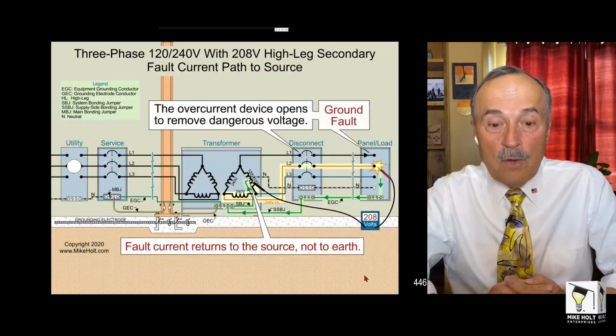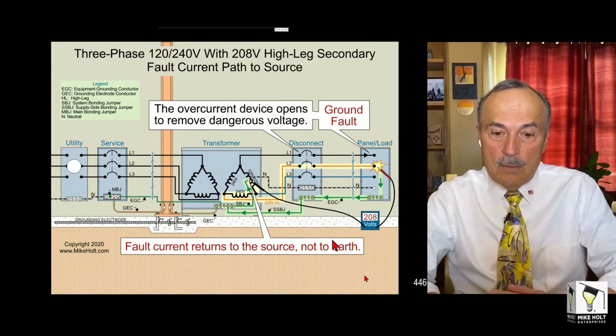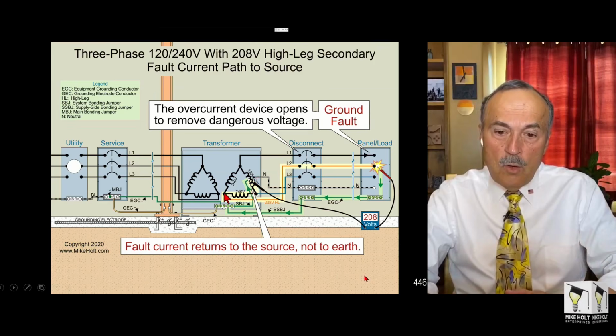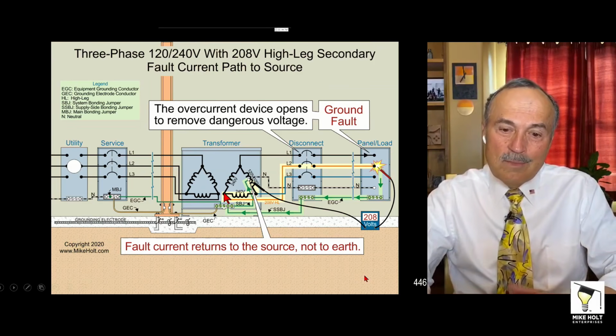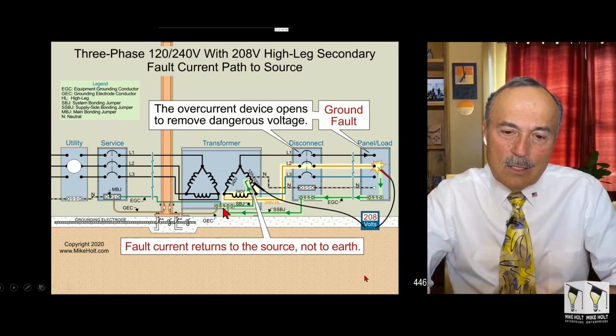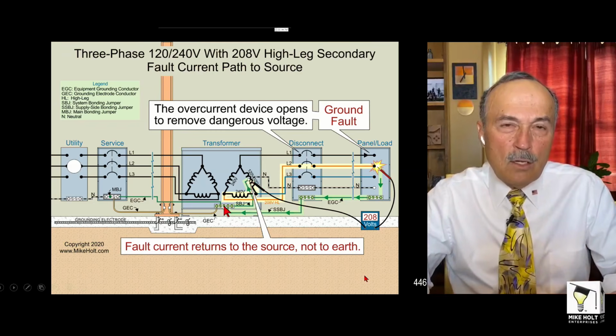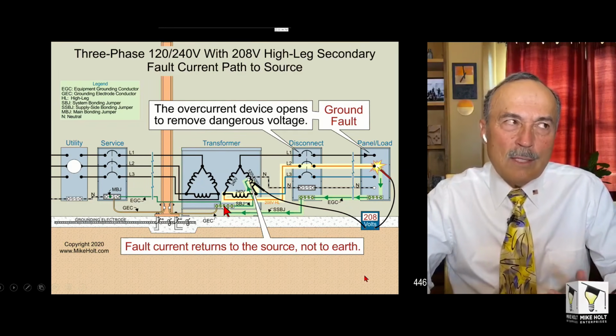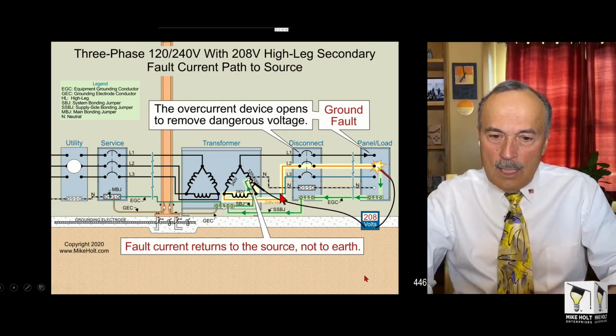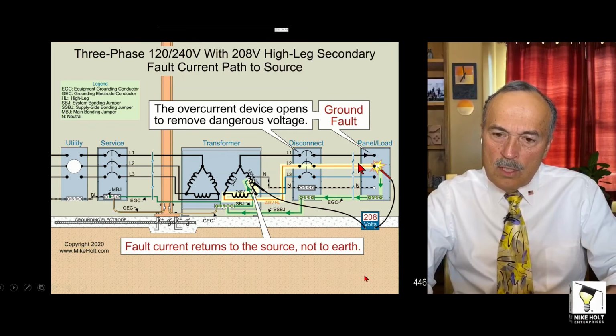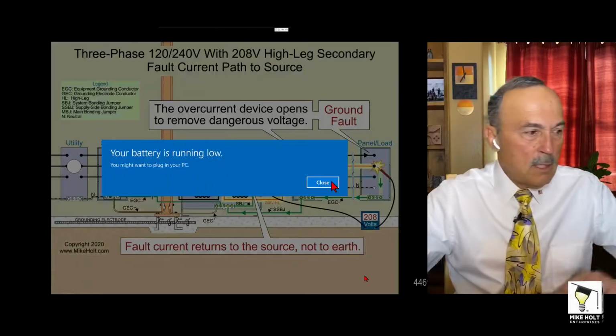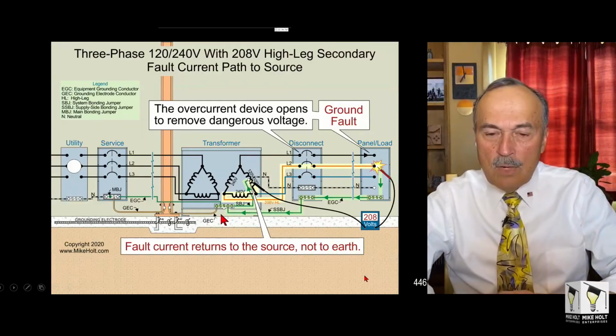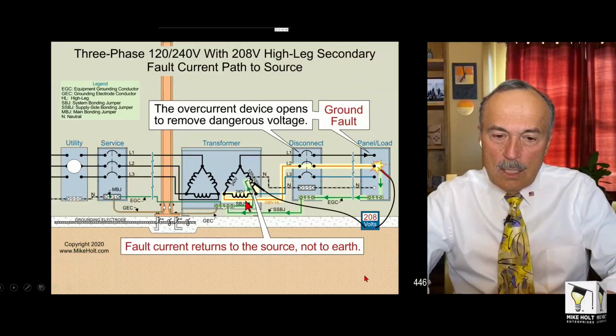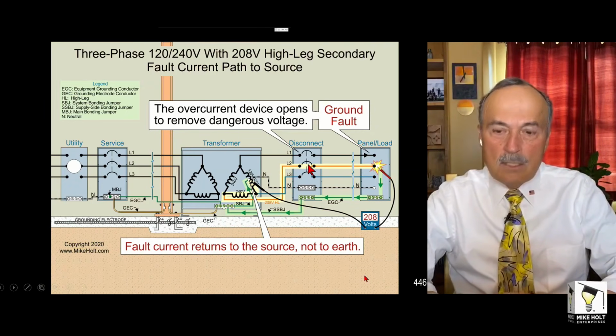We have a high leg fault, using the worst case scenario. Well, then that's going to be 208 volts to ground. When I say ground, we're talking about where the X0 is connected to the case of the enclosure. It's not really ground, but we call it ground. Well, then electrons leave the transformer, go to the overcurrent device. There's a ground fault, travels along. Oh, my battery is getting slow here. It travels along the effective ground fault current path, and then you trip the overcurrent protection device.